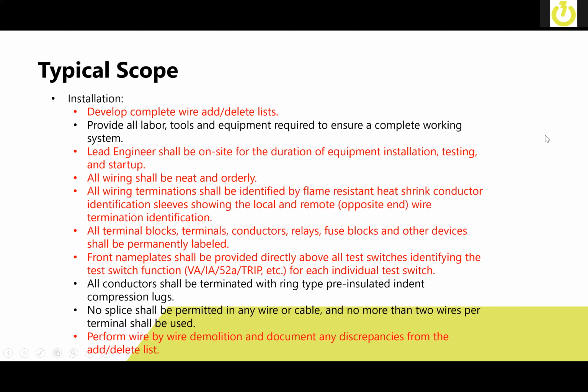Another thing that is suggested is to do front nameplates directly above all test switches, identifying the test switch function, for instance, voltages, currents, breaker status, trips, etc. for each individual test switch, again, trying to minimize the time that a technician would have to pull out a drawing to be able to isolate whatever he needed to isolate or to do troubleshooting or testing.